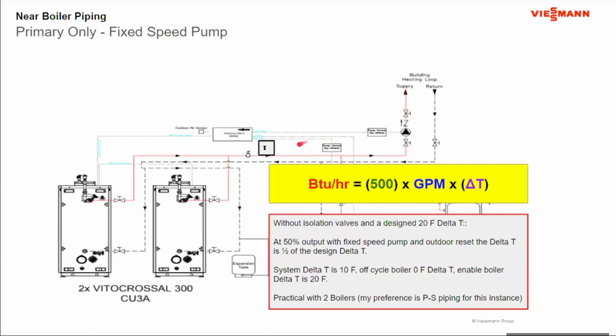So if I have 10 degrees here, I pick up nothing through the off-service boiler. The on-service boiler is going to run at a 20-degree delta T, much more manageable. So this is what makes this system be able to work under those conditions. When I run 2 boilers, I get my design delta T across both boilers. But when I'm only running a single boiler, the delta T has to be high enough to give me the proper common supply temperature going out to the building. Again, this is a specialized case, but I always like to bring it up because it happens. It comes up enough that it's part of the discussion.